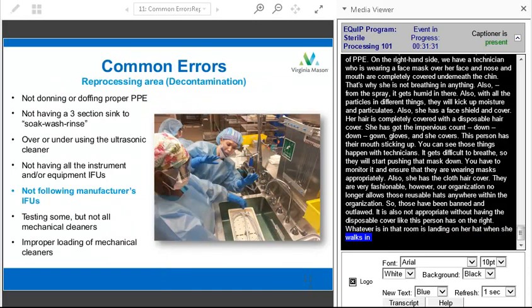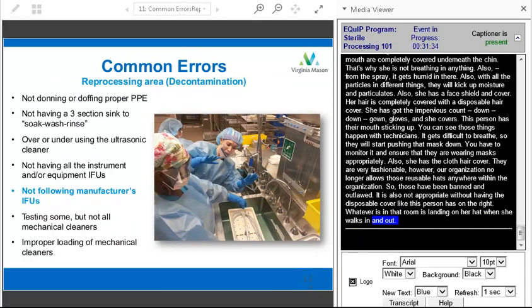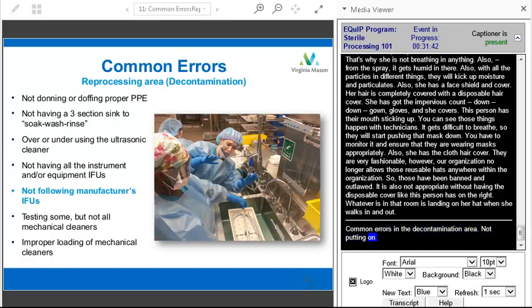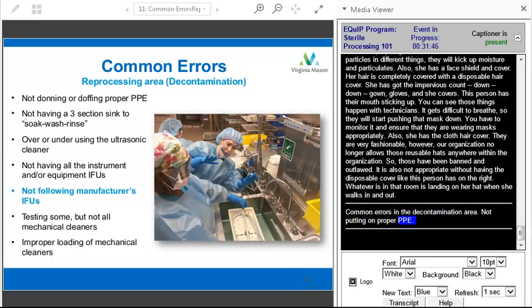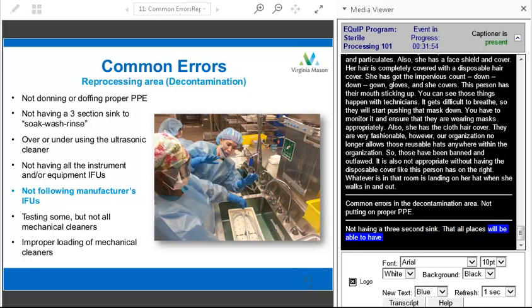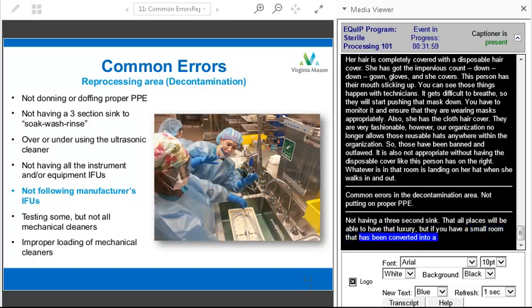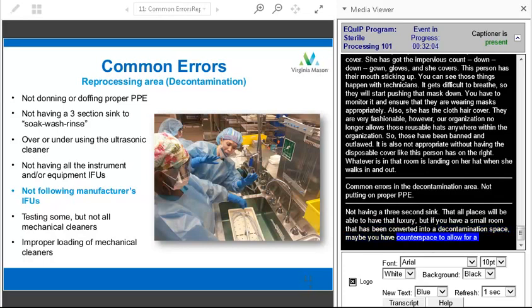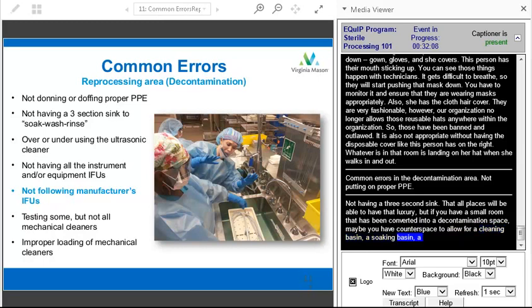All right, so common errors in the decontamination area. Not donning and doffing proper PPE, so we called out the proper wearing of it. Not having a 3-section sink: soak, wash, rinse. Now, not all places will be able to have that luxury, but if you have a small room that's been converted into your decontamination space, maybe, if you have the counter space, allow for a cleaning basin, a soaking basin, a rinsing basin. Those are all at least kept separate, and that your dirty to clean flow is maintained.